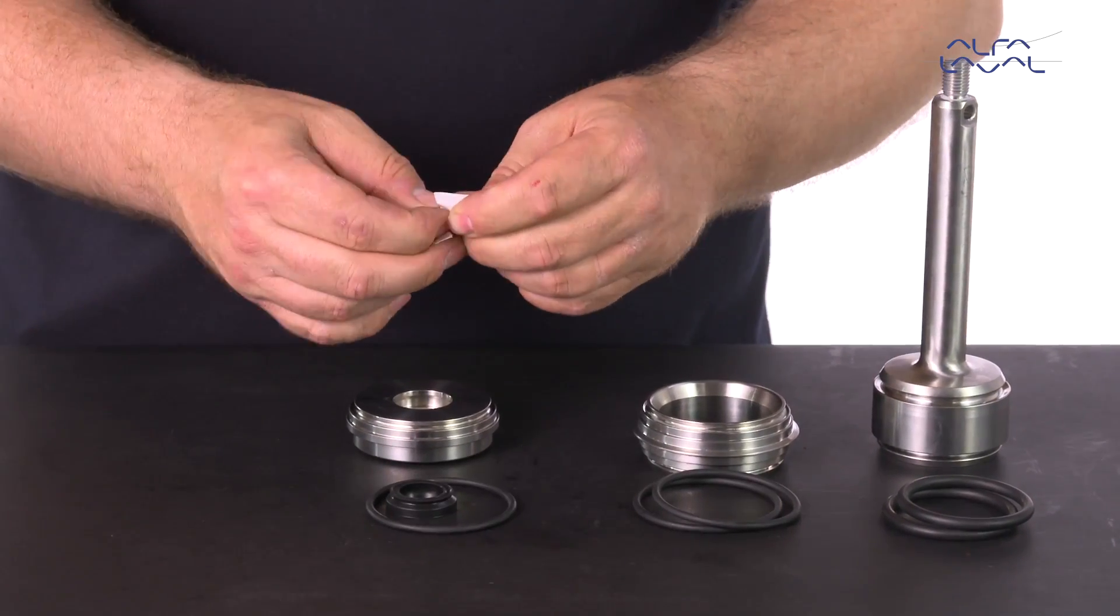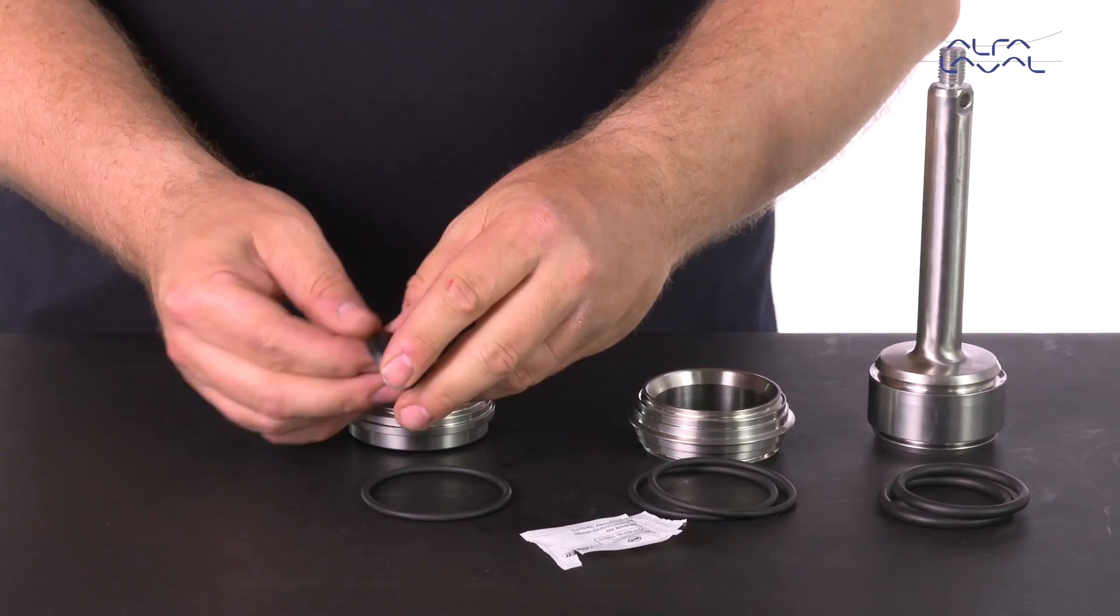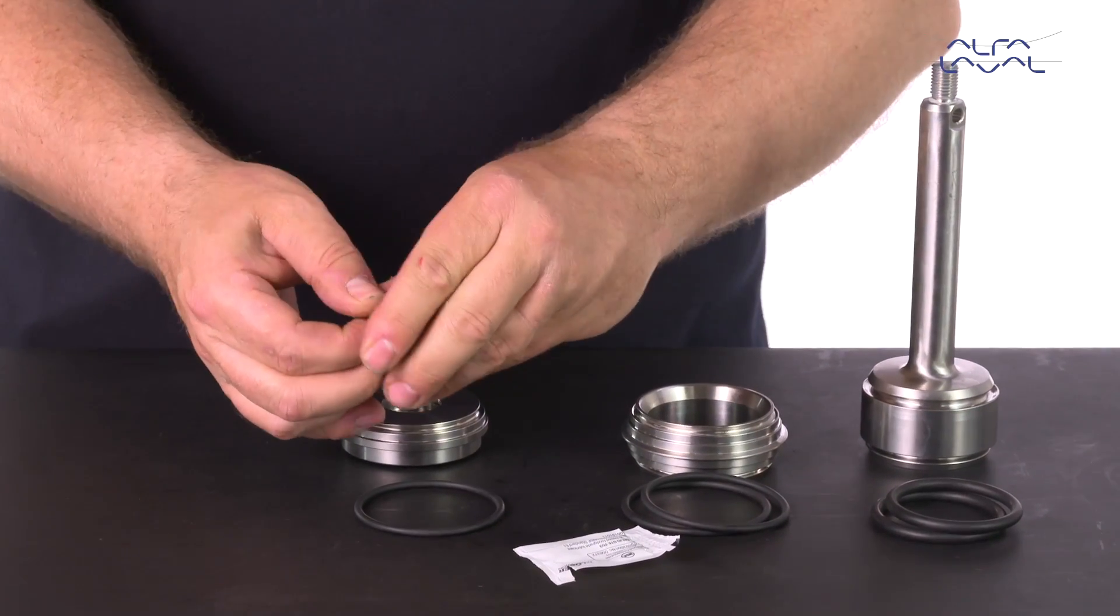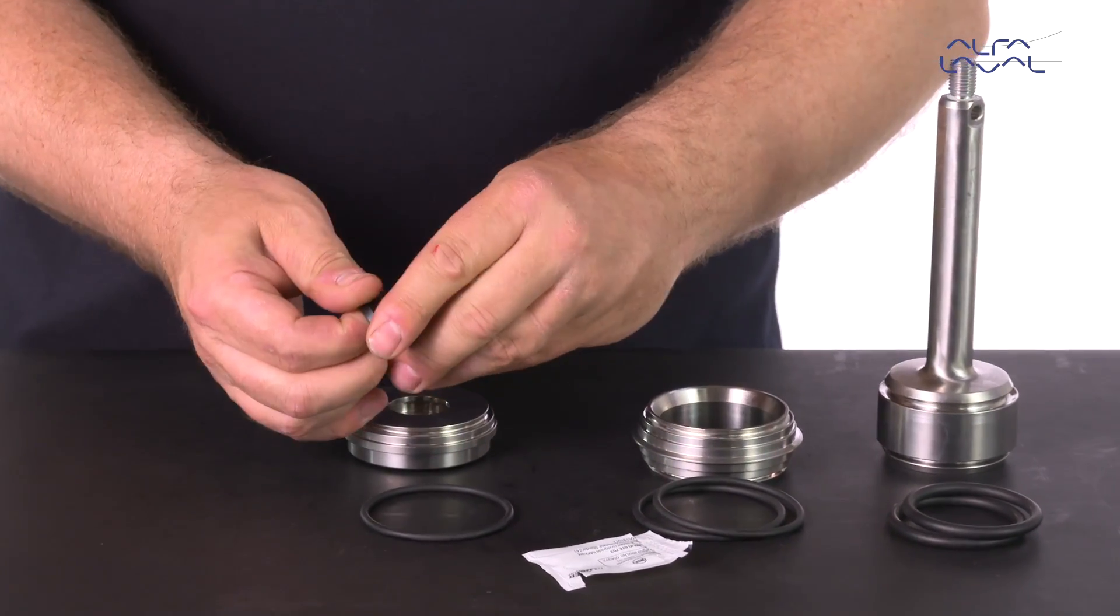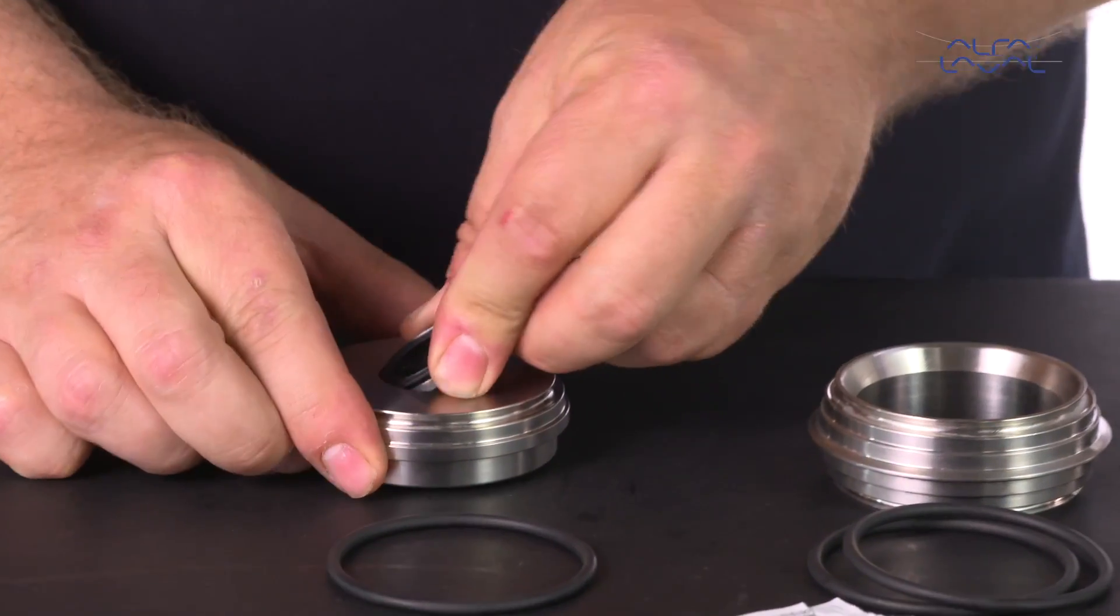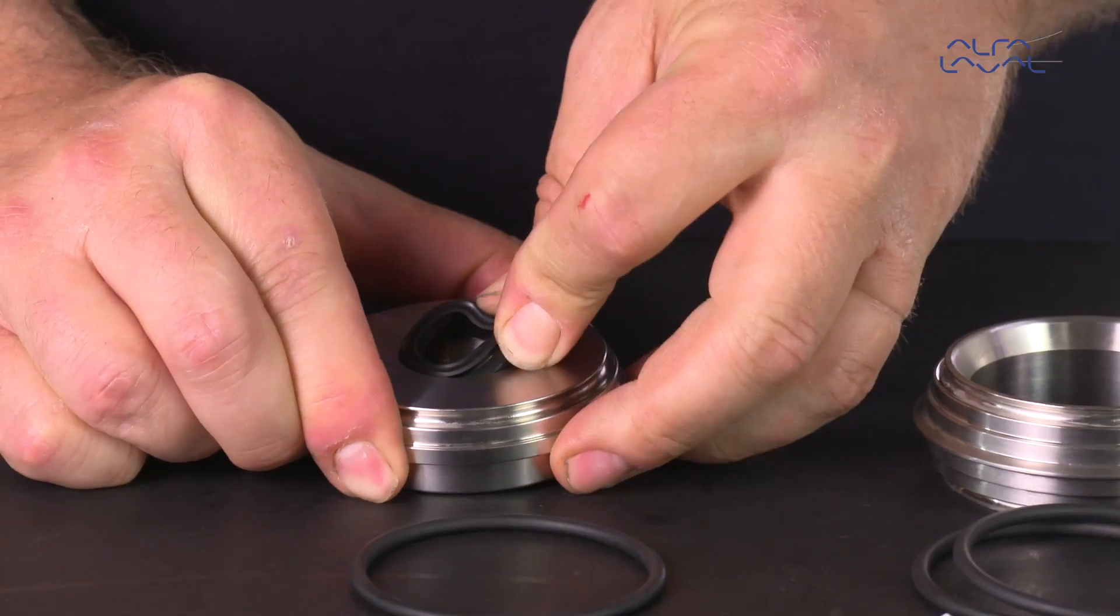After dismantling the valve, remove all product wetted seals. We are now ready to replace the seals starting with the lip seal. First, lubricate and mount the lip seal in the sealing element.